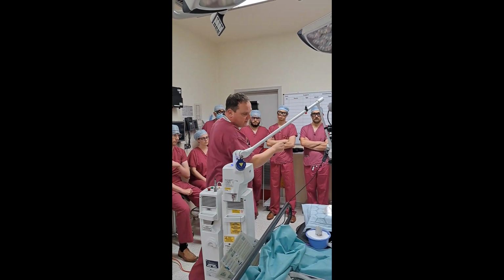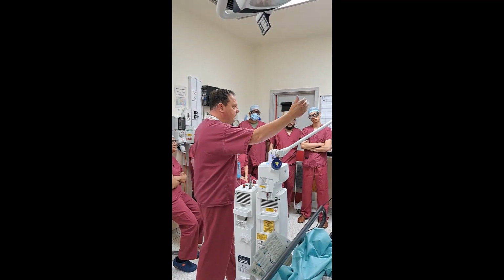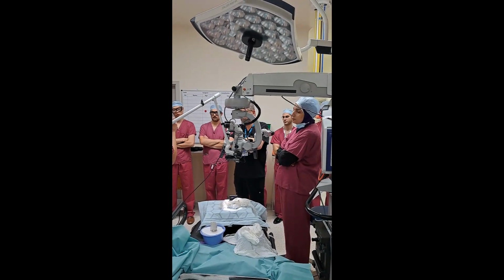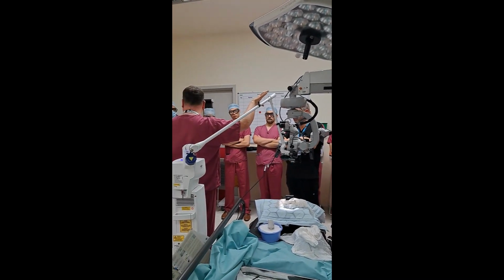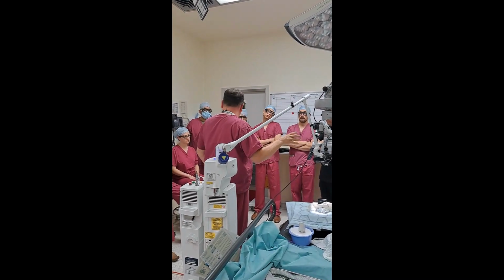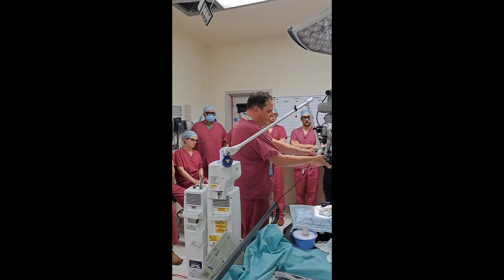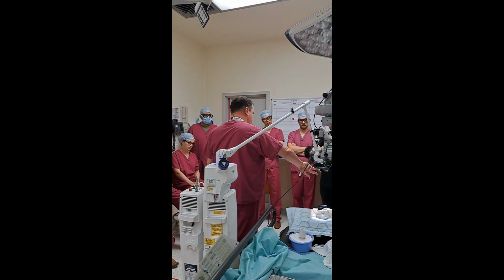We have the arm here, which is a series of mirrors all the way up, which allows the beam to travel right to the end and out, and so we aim the beam exactly where we want it. Very fragile, because obviously the mirrors can go out of placement. So these really do need a lot of care. What we have is the free beam arm here. This is connected to a scanner, which in turn is connected to what we call a micro manipulator.